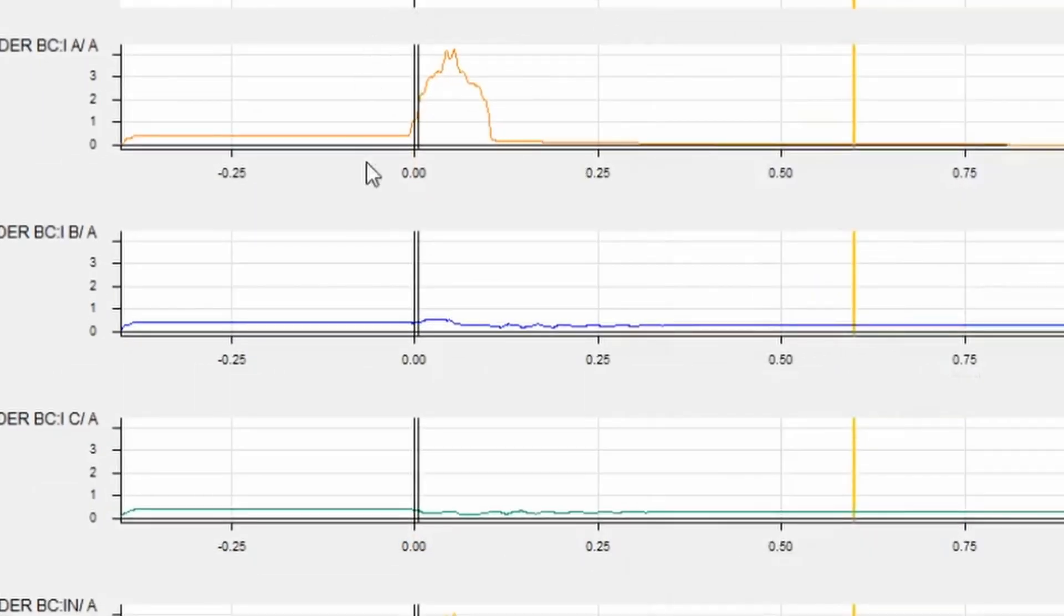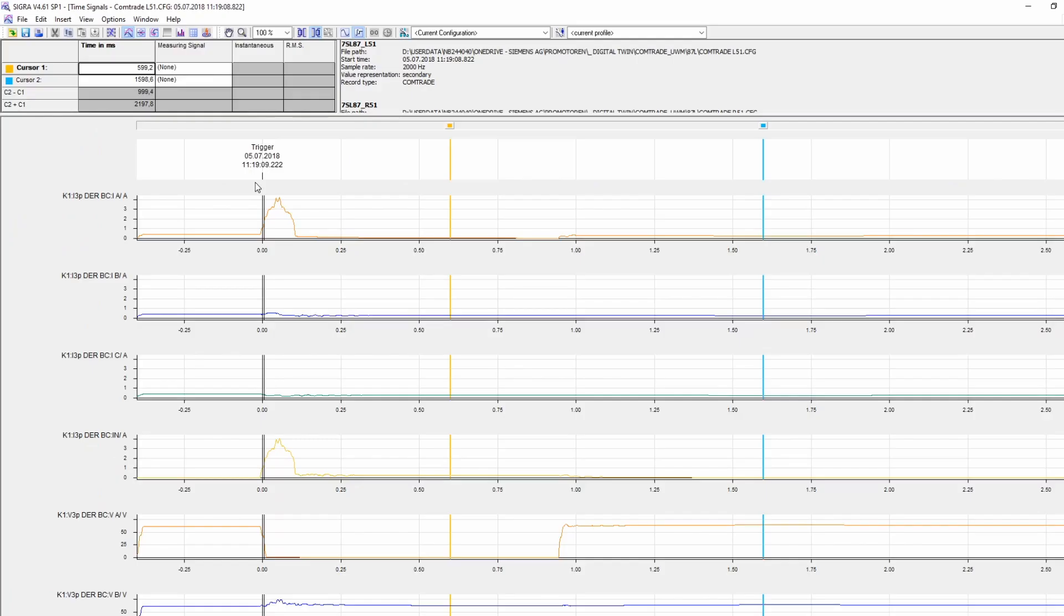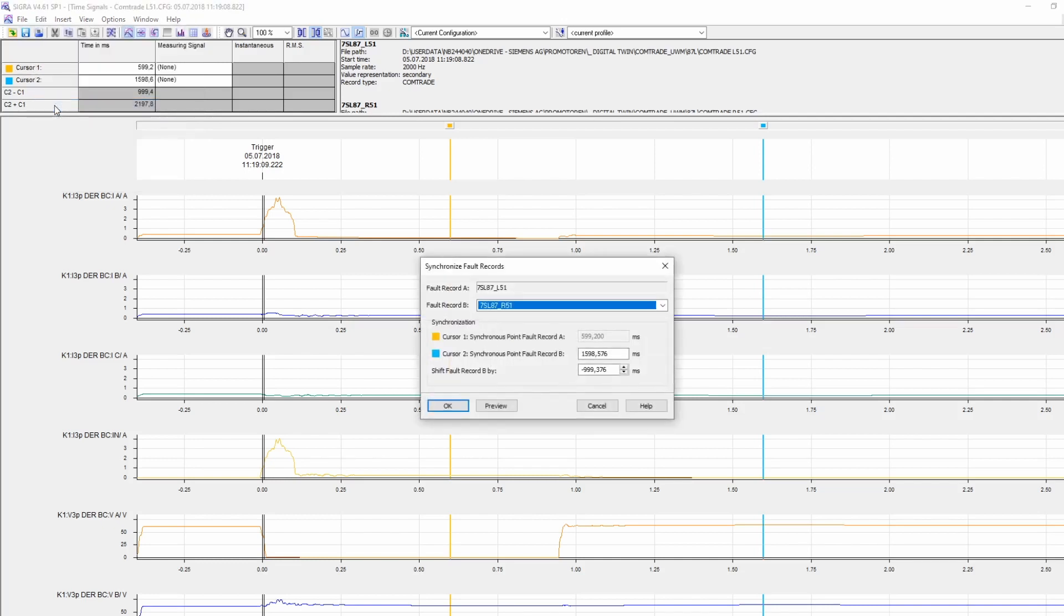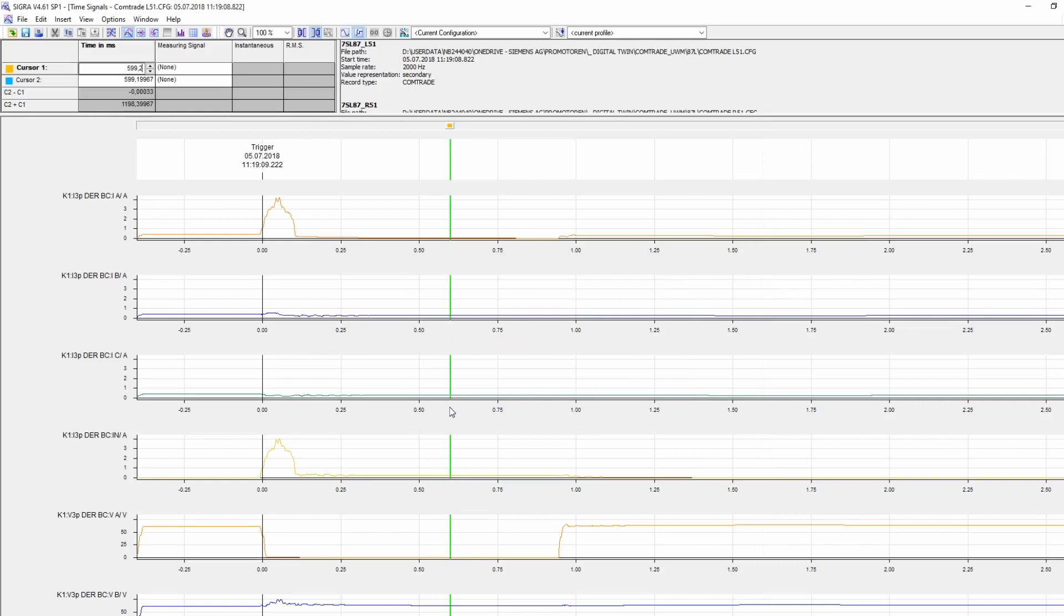But if you look at here, we got some time differences. So it is quite important that we synchronize the fault records. And for that, we go to Edit, Synchronize Fault Records. So now that the signals got aligned, we are ready to export the file.